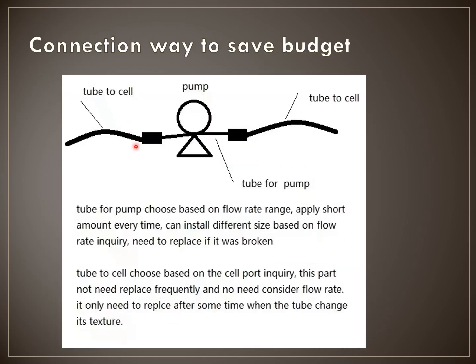Another way to save budget is to use extension connections to isolate the tube inside the pump from the tube going to the device. Then every time you replace the tube, you just replace a short length — no need to replace the entire tube and affect the whole system. You can contact us to source suitable adapters for your system.